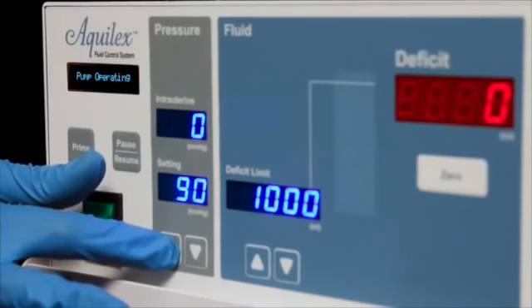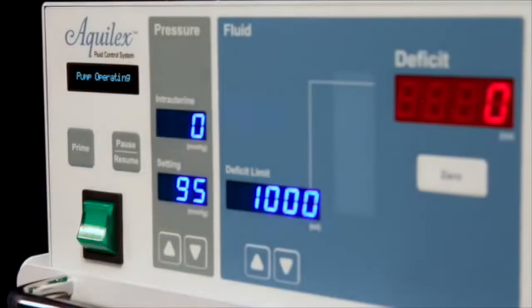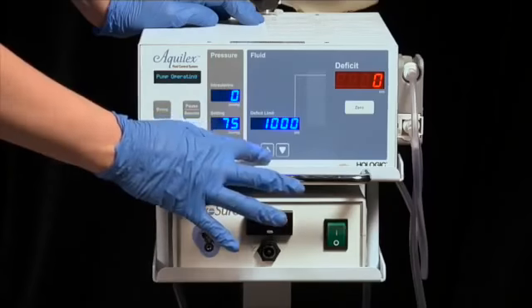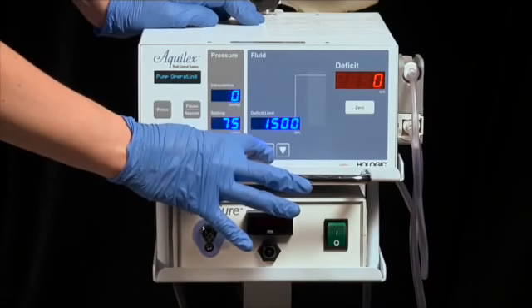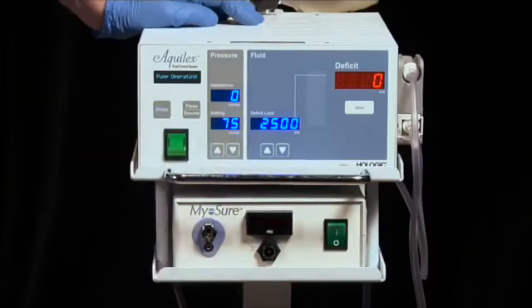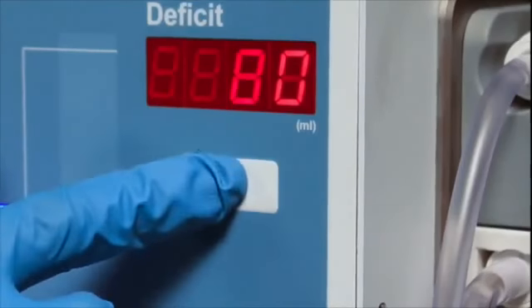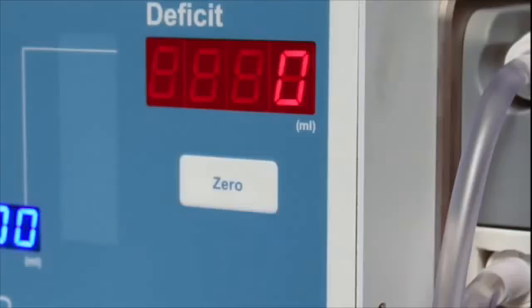Set the intrauterine pressure using the up and down arrows to adjust. Set the appropriate deficit limit using the up and down arrows to adjust. Press the Zero button to reset the deficit to 0 once the priming has completed.